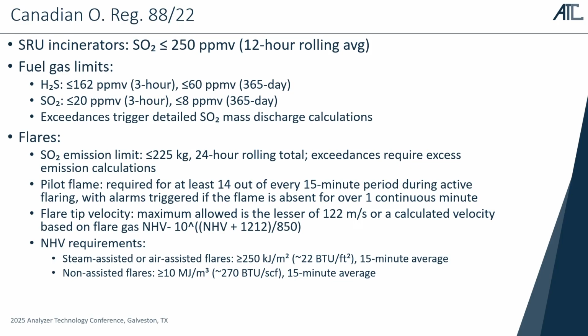Additional requirements are NHV, net heating value. So they mandate the refineries to calculate the net heating value for their flares, and it depends on steam assist or non-steam assisted. And there are also requirements for the pilot flame to be on for at least 14 out of every 15-minute period, and to measure flare tip velocity. And there are limits, and then alarms for that as well, should you cross that limit or that threshold.